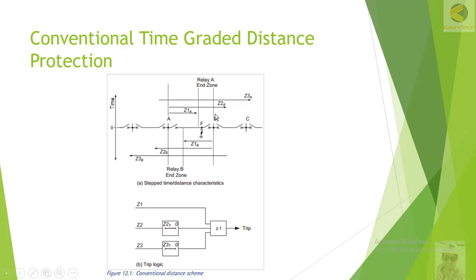If Zone 1 were set to 100% of the line between A and B, any fault on that line would trip in Zone 1, which is set to 0 milliseconds — that is, instantaneous. The 20% margin is kept to account for relay error, CT error, VT error, and variable arc impedance or ground impedance. With experience, it is known that underreaching and overreaching can each be 10 to 15%.